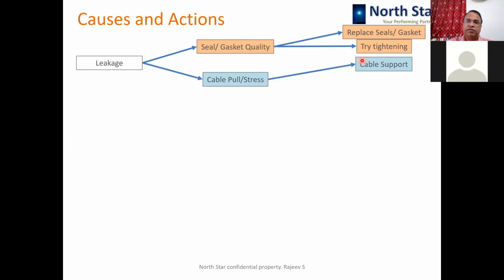If you tighten it, okay, fine, you can tighten it, but be sure that after some time you will again get leakage from the stem joint, because gaskets are single-use components. They cannot be reused. They cannot be retightened. A gasket makes a seat at the place, and it forms in that place, so that form cannot be changed by tightening. The form gets disturbed and the leak will stop for the time being, but then it will occur with more severity. So the long-term, permanent solution for an oil or gasket leak is replacement of the gasket only.